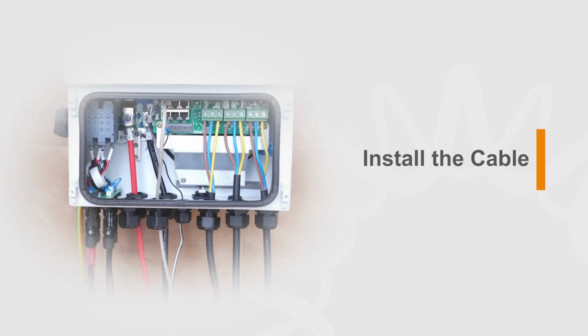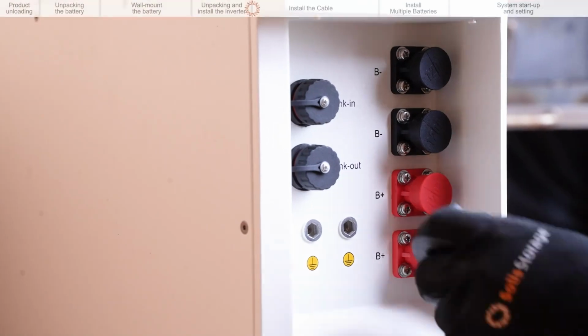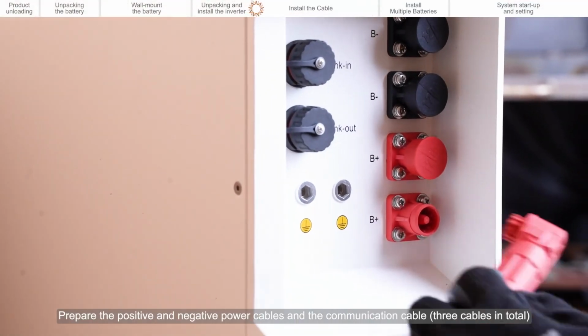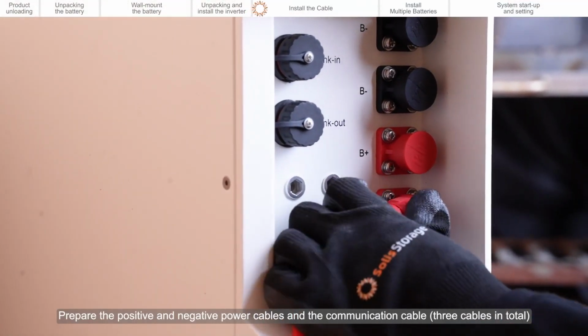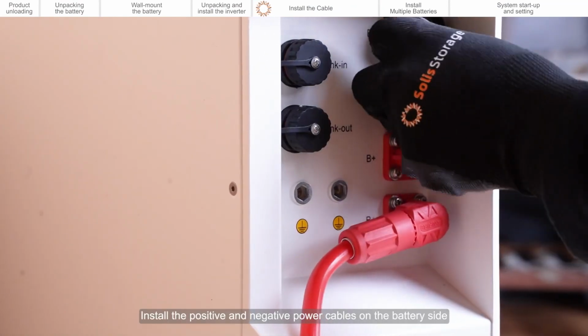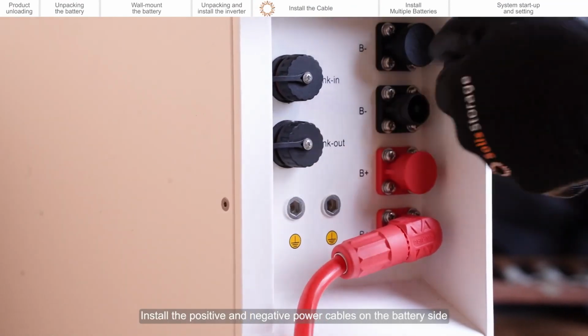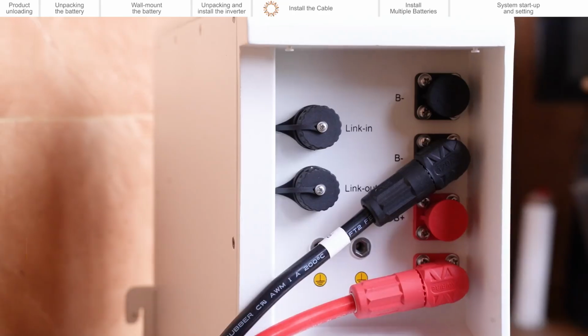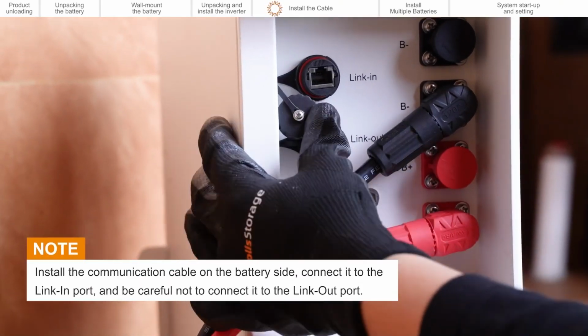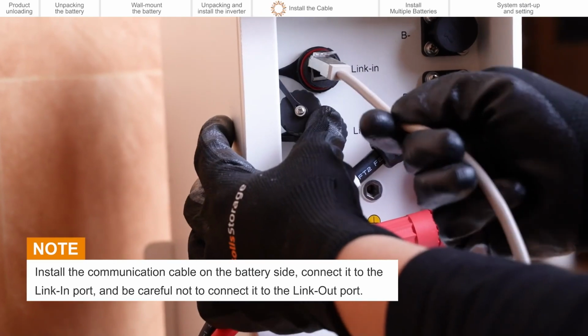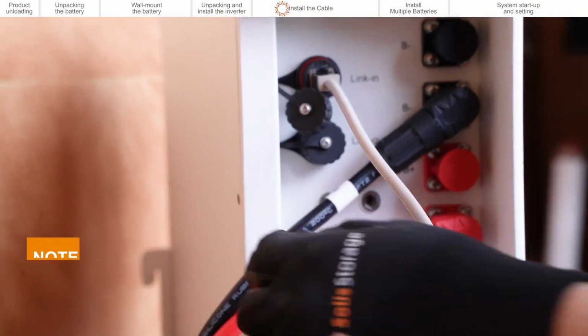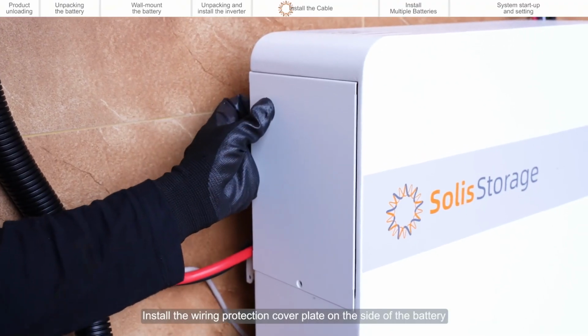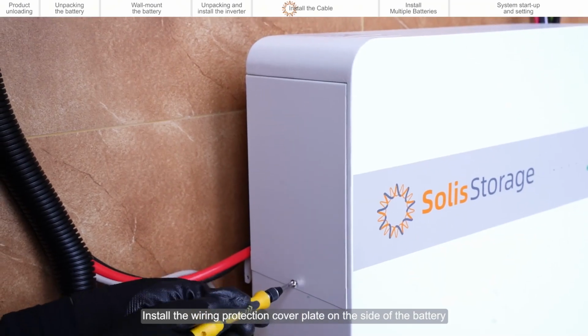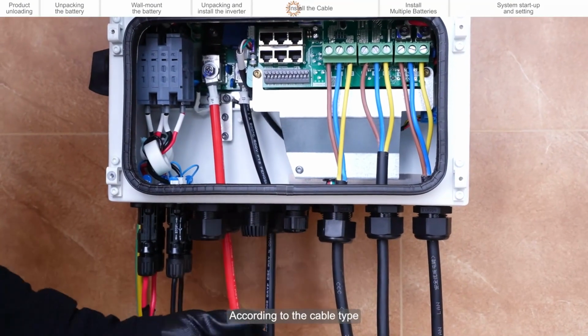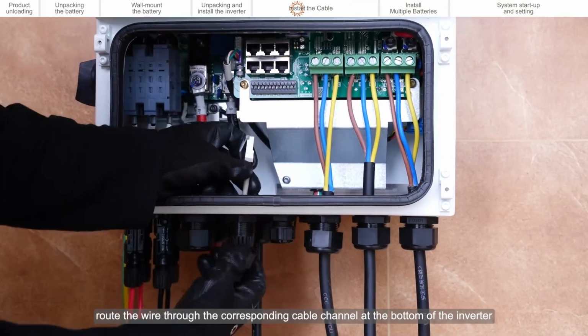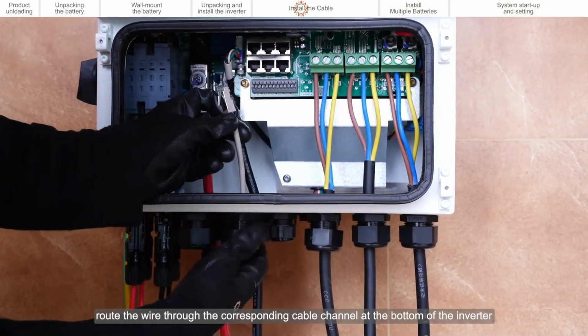Install the cable. Prepare the positive and negative power cables and the communication cable. Install the positive and negative power cables on the battery side. Install the wiring protection cover plate on the side of the battery. According to the cable type, route the wire through the corresponding cable channel at the bottom of the inverter.